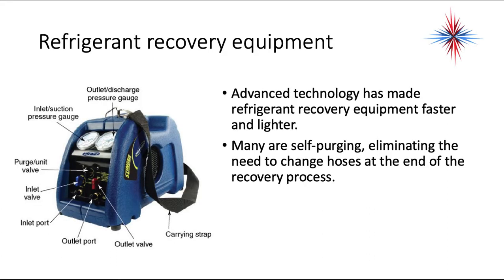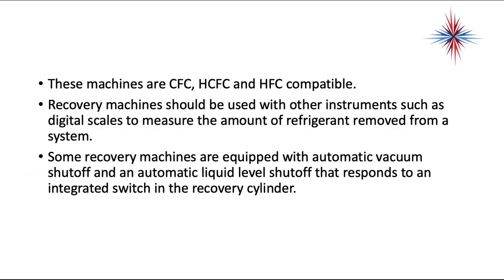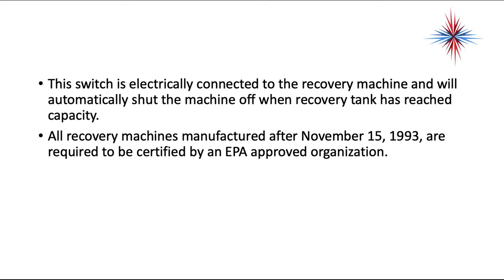Recovery equipment has changed over the years. Advanced technology has made refrigerant recovery equipment much faster and lighter. Many are self-purging, eliminating the need to change hoses at the end of the recovery process. These machines are CFC, HCFC, and HFC compatible. Recovery machines should be used with other instruments such as digital scales to measure the amount of refrigerant removed from a system. Some recovery machines are equipped with automatic vacuum shutoff and an automatic liquid level shutoff that responds to an integrated switch in the recovery cylinder. This switch is electronically connected to the recovery machine and will automatically shut off the machine when the recovery tank has reached capacity. All recovery machines manufactured after November 15, 1993 are required to be certified by an EPA-approved organization.